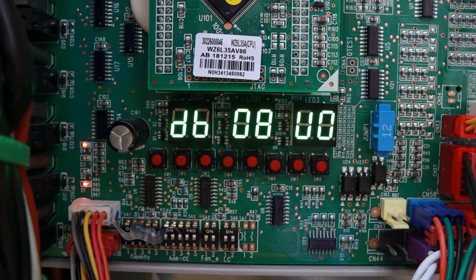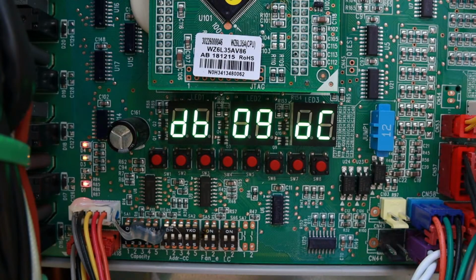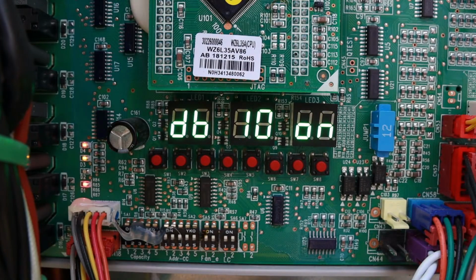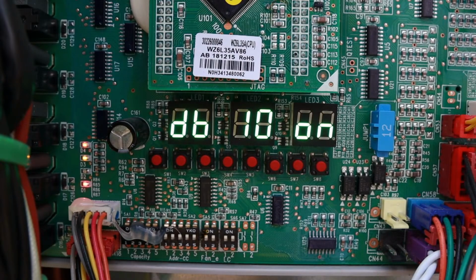Because this system has been commissioned before, I'm able to press confirm SW7 to move up to the next step. But in your case, if it's a brand new unit, just wait the 8 hours, and then the system will automatically jump to step 9. Step 9 is a quick refrigerant charge check, and then it will jump into step 10. On step 10, the system is checking that the valves are fully open. You will hear the compressor kick on, as well as the fan motors, and the system will run for a few minutes. Make sure that you open the valves before you start the commissioning cycle. Otherwise, you're going to have an issue here.